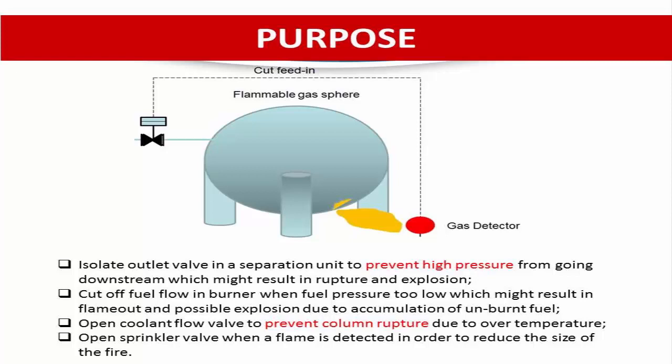Examples of potential safety instrumented functions include: isolating the outlet valve in a separation unit to prevent high pressure from passing downstream, which might result in rupture and explosion; and cutting off the fuel flow to a burner when fuel pressure is too low, which might result in flame-out and possible explosion due to accumulation of unburned fuel in the burner.